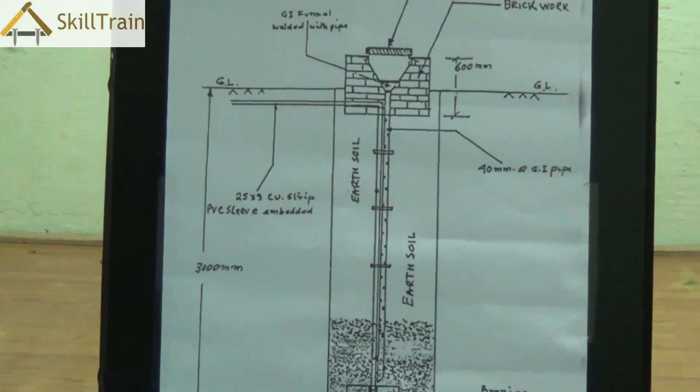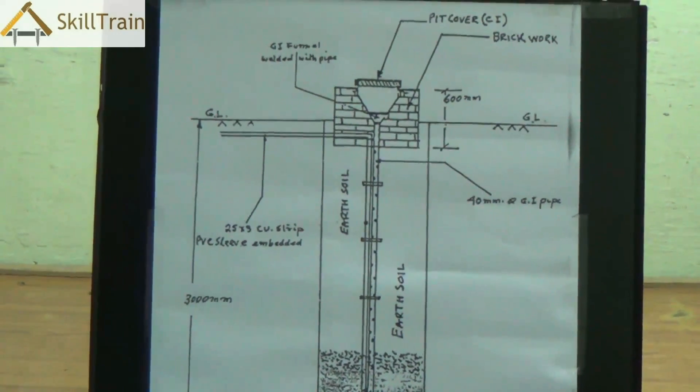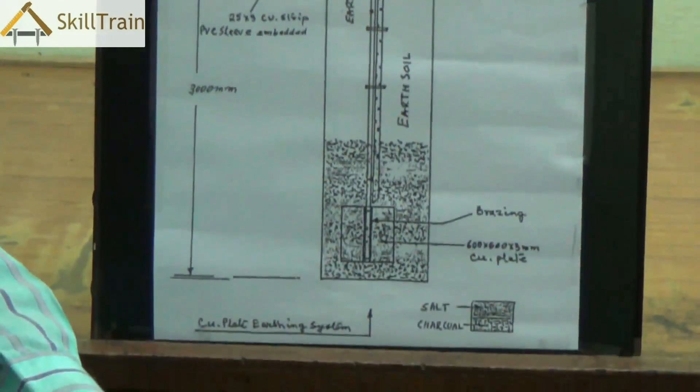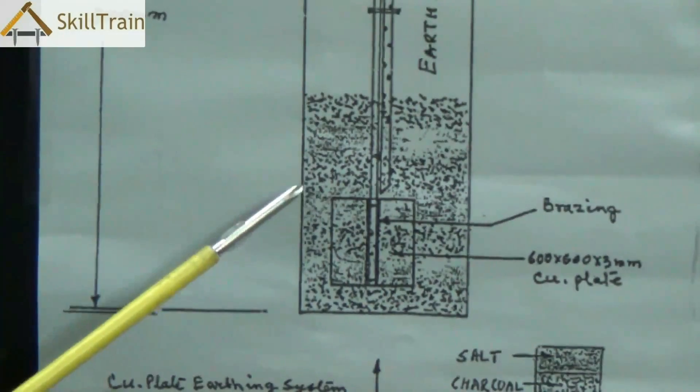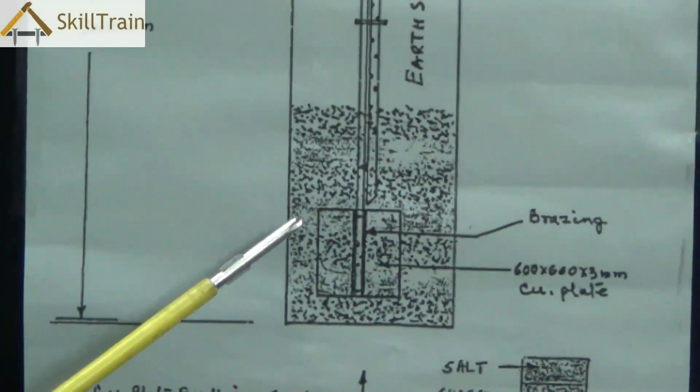In order to do this type of earthing we dig around 4 to 7 feet inside the soil from the ground level. We go deeper to about 4 to 7 feet and underneath we place a copper plate or a GI plate.